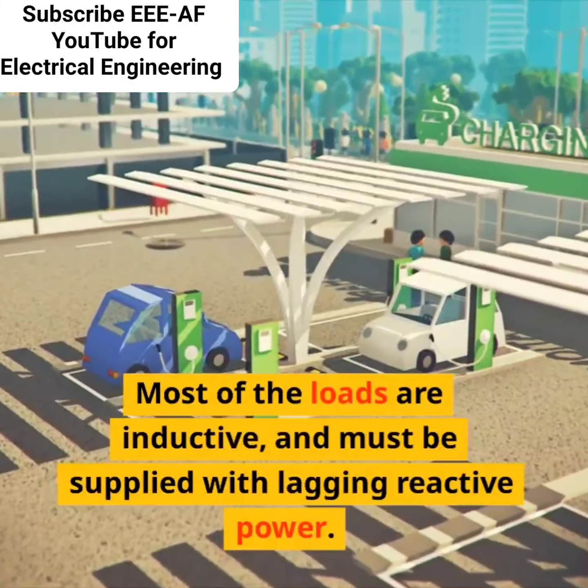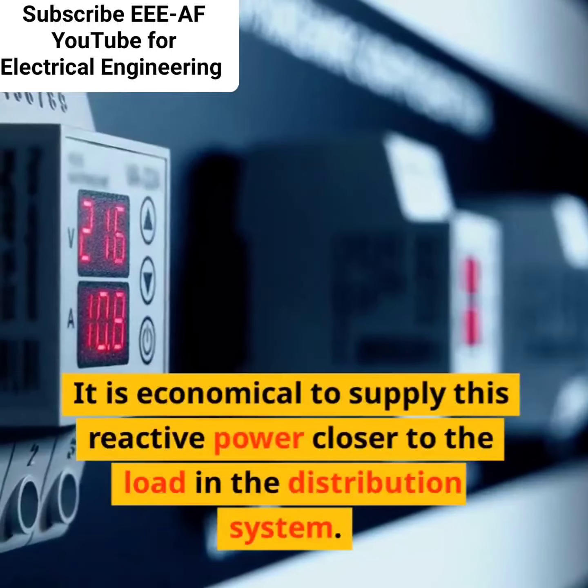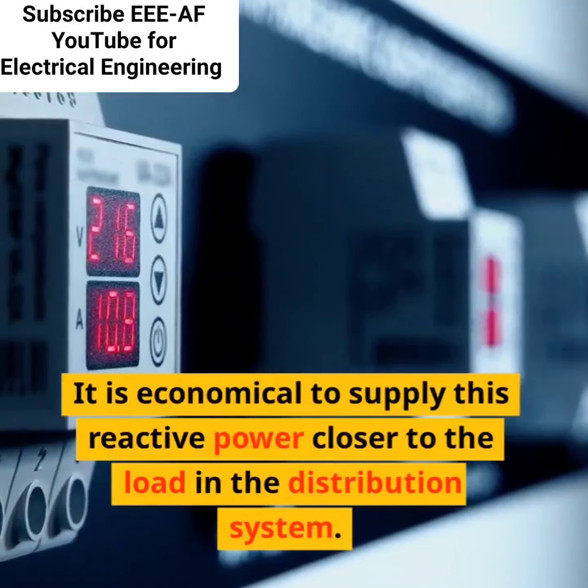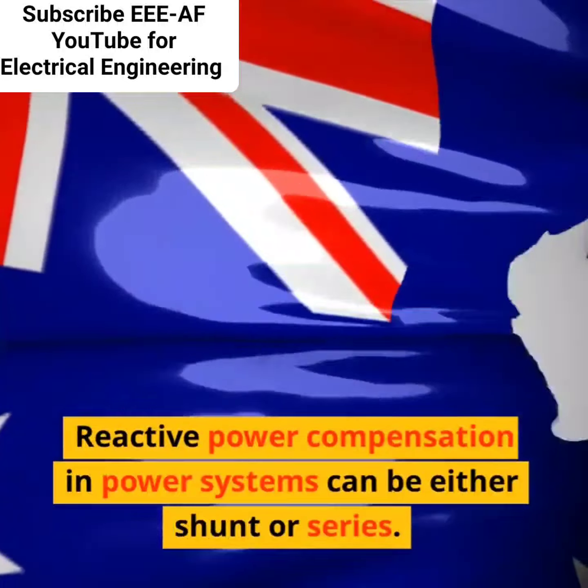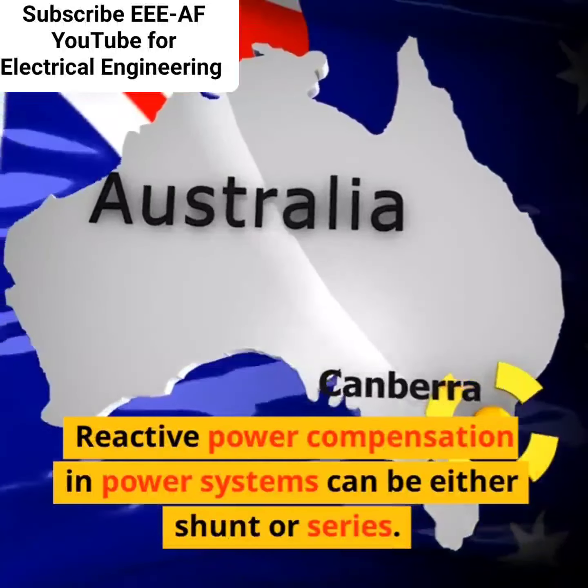Most of the loads are inductive, and must be supplied with lagging reactive power. It is economical to supply this reactive power closer to the load in the distribution system. Reactive power compensation in power systems can be either shunt or series.